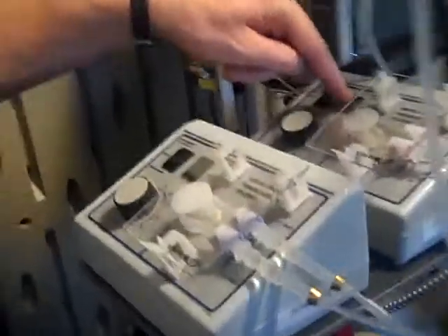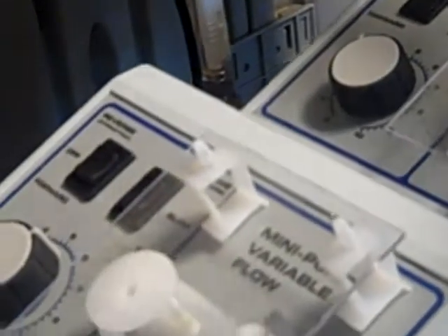We also want to make sure the power strip is on for the entire G2. Okay. Yes, we also want to make sure that the supply is full. We'll check that. Like ionized water, right? Deionized water. Yeah, deionized water. So you want this to set at forward, slow. That's where the button's in the middle, and set to about 3. And then you'll check your rotameter for the proper flow, which you'll determine with a little bit of experience.